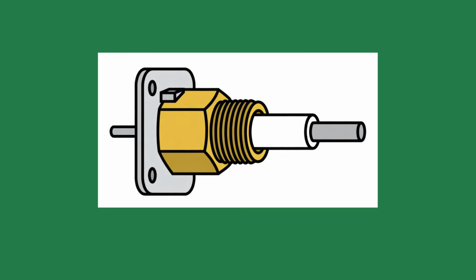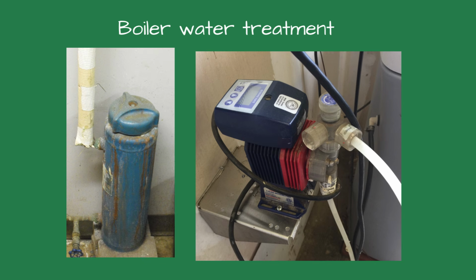The following are some of the common failure modes of probe type low water cutoffs. Boiler water leaves deposits on the probe that can insulate the tip, causing false low water trips or, less commonly, preventing a trip when it should. Cleaning the probe by removal and inspection is often required annually on commercial boilers and every few years on residential ones. Low conductivity water: very pure or heavily treated water may not conduct electricity well enough, which can affect reliability.